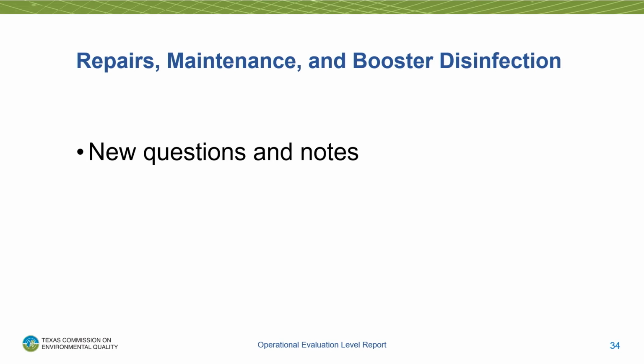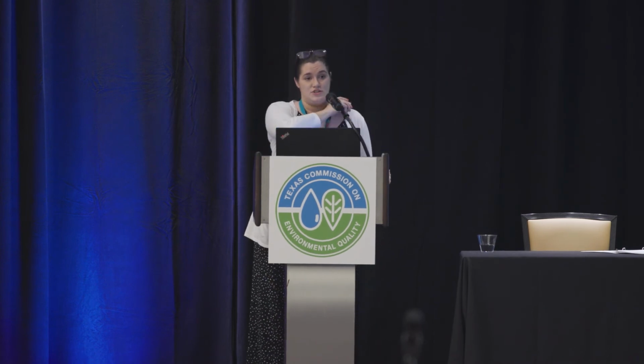So we've added new questions for repairs, maintenance, and booster disinfectant. Specifically about booster disinfectant: are you boosting with the same type of disinfectant as you're using in the treatment? Because some systems actually do make it free chlorine, not really realizing it. They think they're just upping the dosage a tiny bit to push it through, but they're really breakpoint chlorinating.